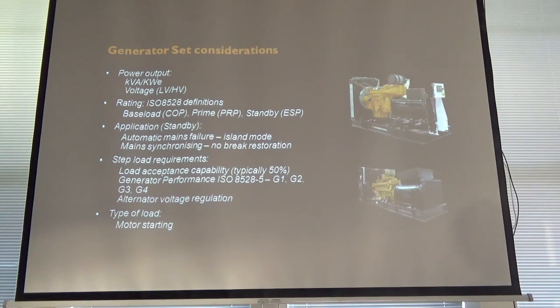Yes? What's the difference with an MTU set? How does it actually take 100% load in seconds? The NFPA 110 specification means, by design to comply with that, it literally is designed for it. So you could say it's over-engineered compared to some of the others, quite frankly.